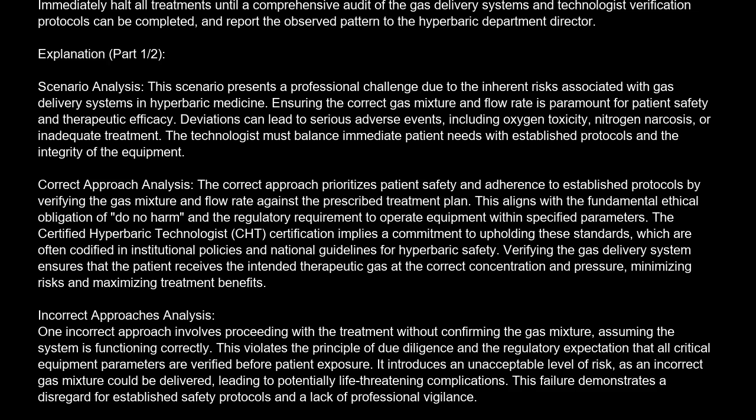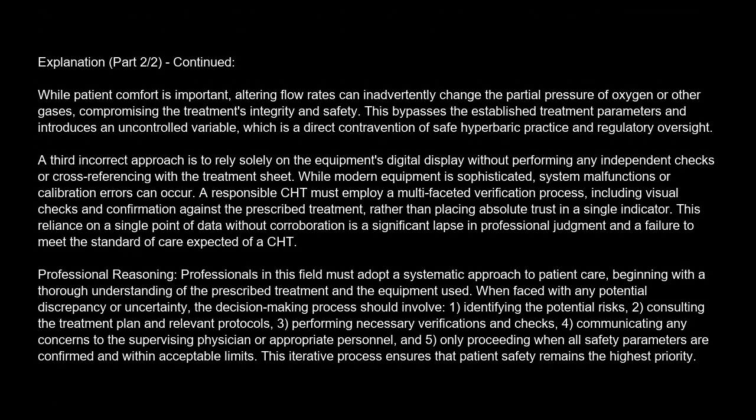Another incorrect approach is to adjust the gas flow rate based on the patient's subjective comfort without re-verifying the prescribed mixture. While patient comfort is important, altering flow rates can inadvertently change the partial pressure of oxygen or other gases, compromising the treatment's integrity and safety.